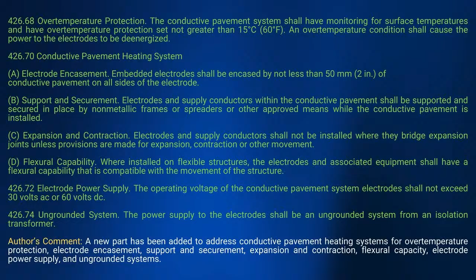And then if you look at the electrode power supply, it tells you it shall not exceed 60 volts DC. And they're also going to tell you that it needs to be supplied from what? An ungrounded system from an isolation transformer. So in other words, you don't want anything grounded here. It's an isolated system.